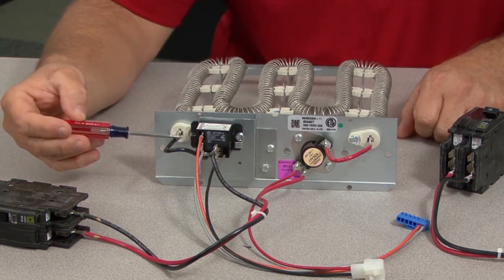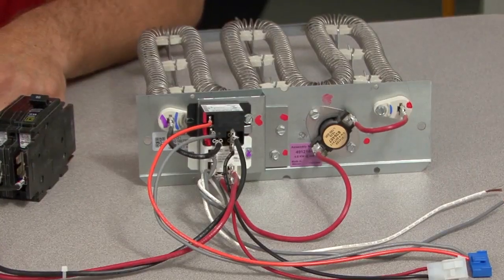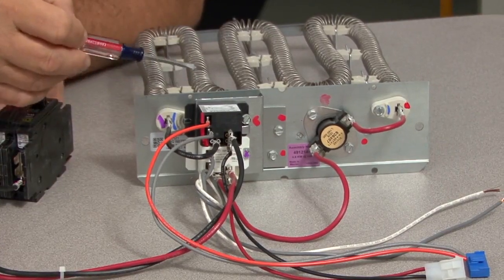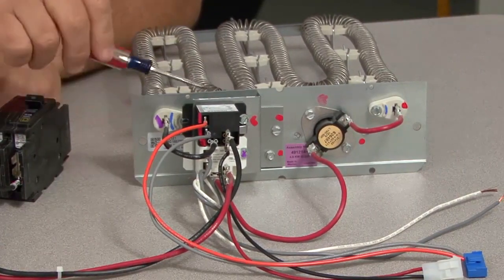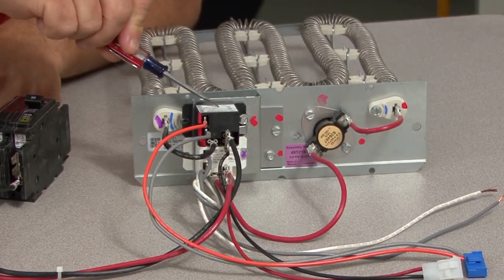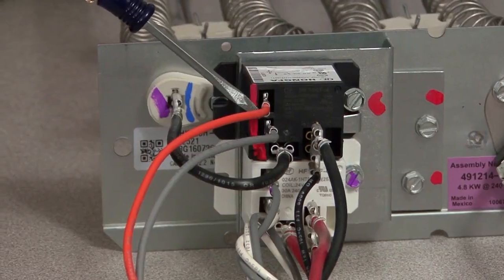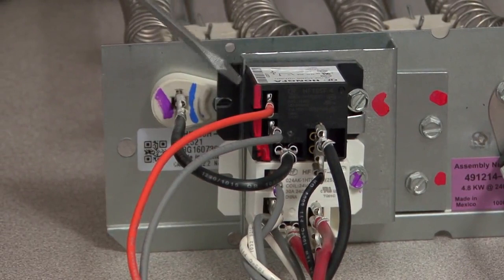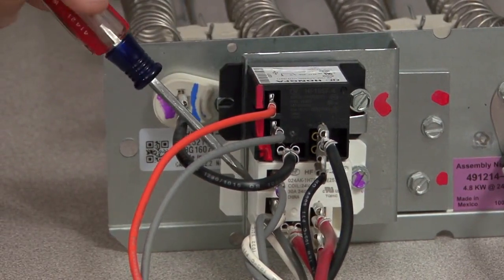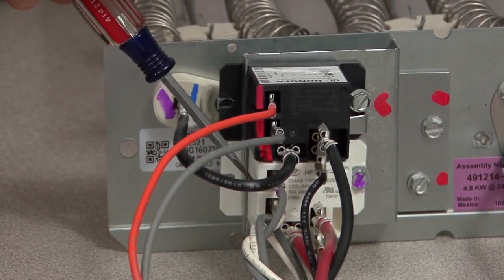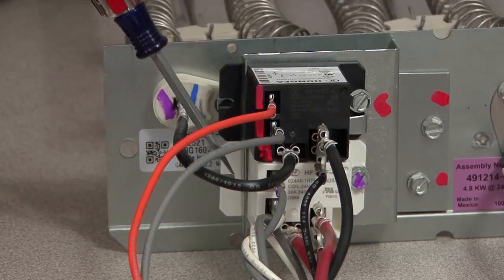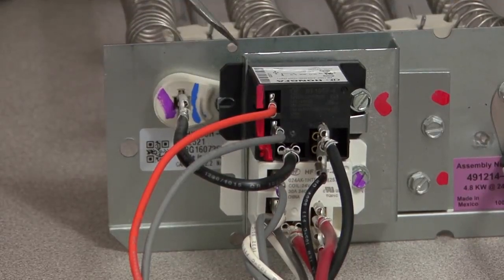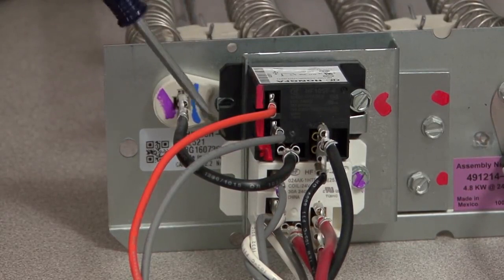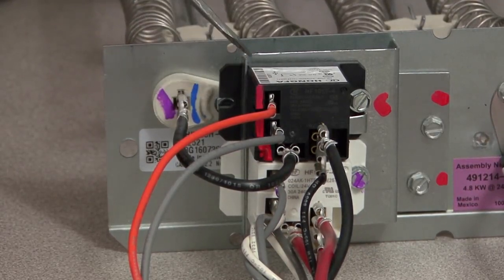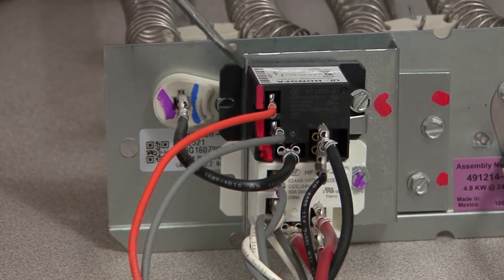So now let's switch up and we'll look at the H8 heater kit. On the H8 heater kit, being another 5 kW, just like the H6 I just showed you, it's got one black DC relay. The control voltage going into that relay is DC voltage, just like it was on the H6. And then you have the white relay, which is an AC controlled relay. So again, if you've got a 5 kW, you're going to have one black and one white. If you had a 10 kW, you'd have 2 blacks and 2 whites. 15 would be 3 blacks and 3 whites, and so on.